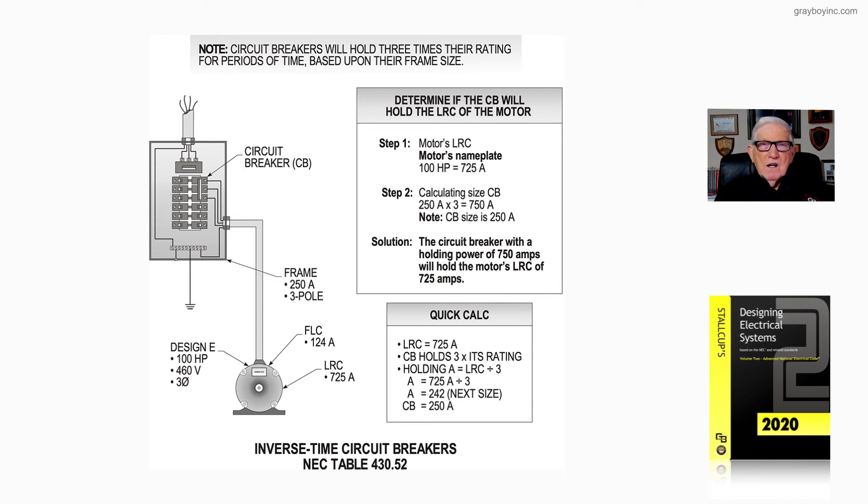Now the question comes up: could I use a 225 or 200 amp inverse time circuit breaker if it'd allow the motor to start and run? Absolutely. There's nothing in the code to prevent that.